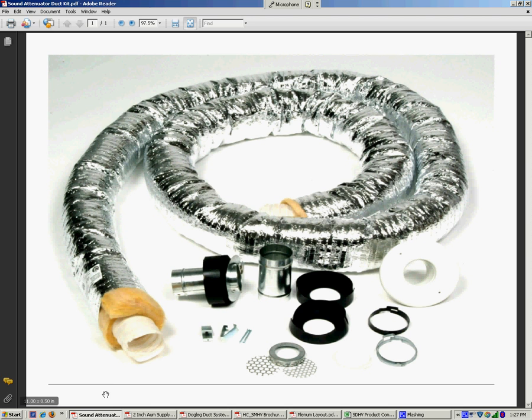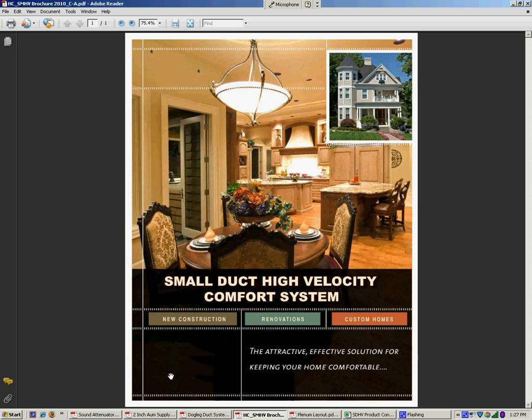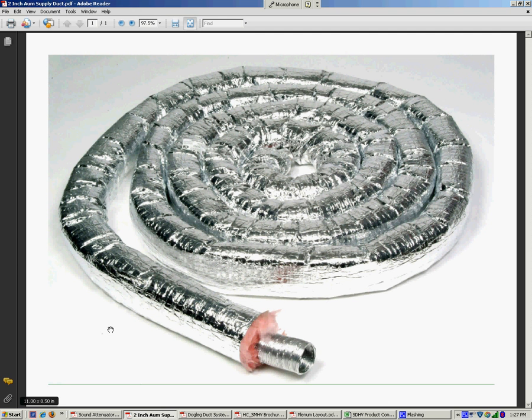Flexible duct comes in two styles. One of them is what we call attenuator, which is used at the minimum of the last three feet of the supply run before it connects to the outlet of the register. You can use up to 12 feet and it comes in 12-foot sections. The other style is flexible aluminum. So when we get into applications where our runs are longer than 12 feet, then from the plenum to the attenuator piping, we're going to use flexible aluminum.